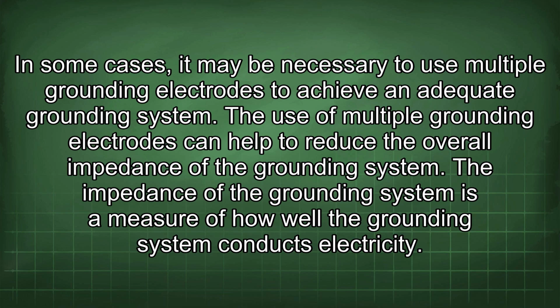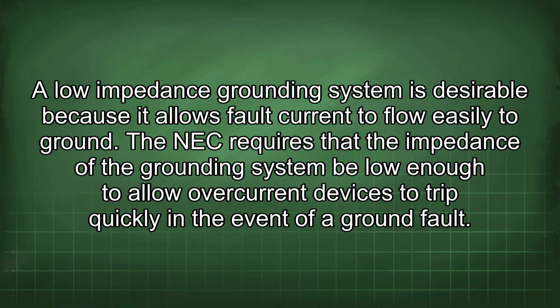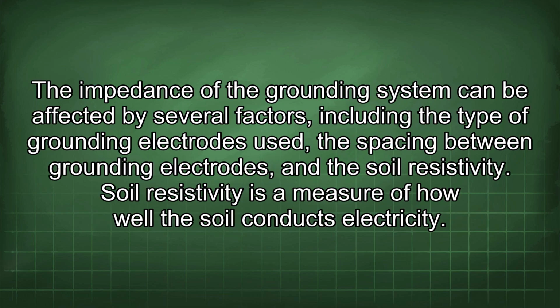The use of multiple grounding electrodes can help to reduce the overall impedance of the grounding system. The impedance of the grounding system is a measure of how well the grounding system conducts electricity. A low impedance grounding system is desirable because it allows fault current to flow easily to ground. The NEC requires that the impedance of the grounding system be low enough to allow overcurrent devices to trip quickly in the event of a ground fault. The impedance of the grounding system can be affected by several factors, including the type of grounding electrodes used, the spacing between grounding electrodes, and the soil resistivity.